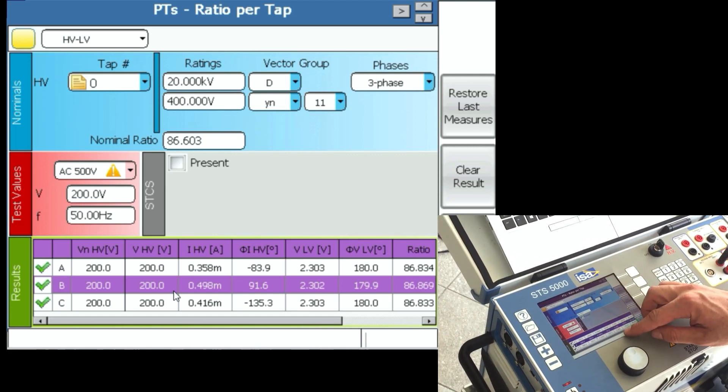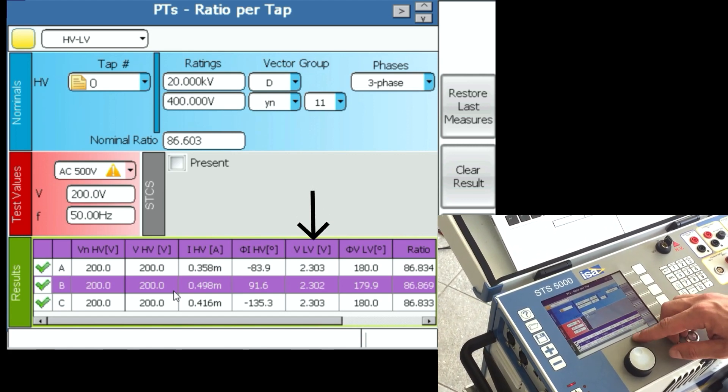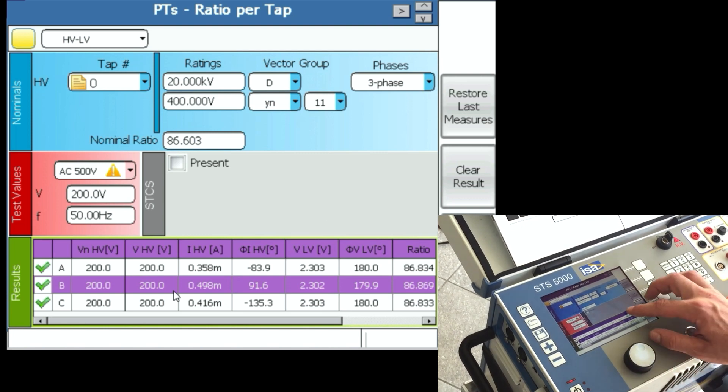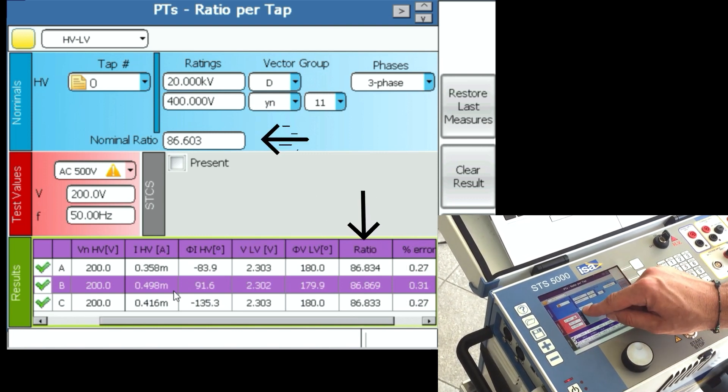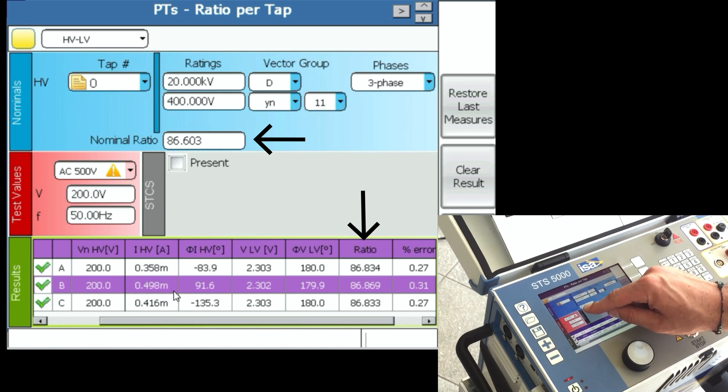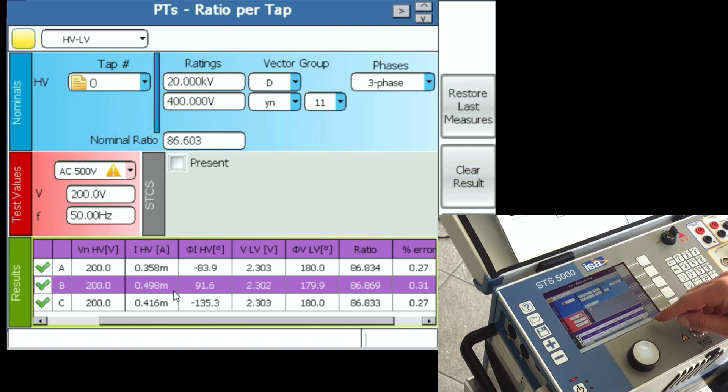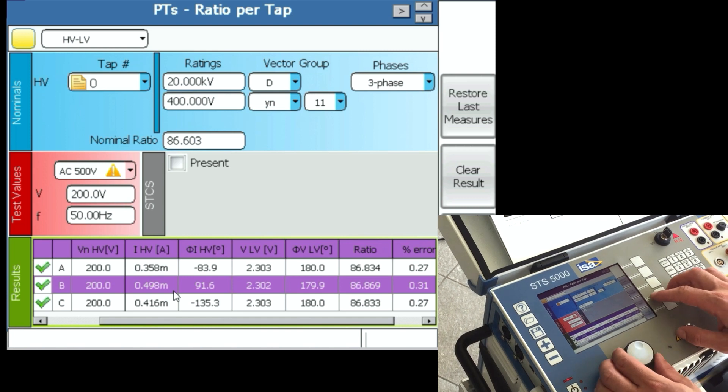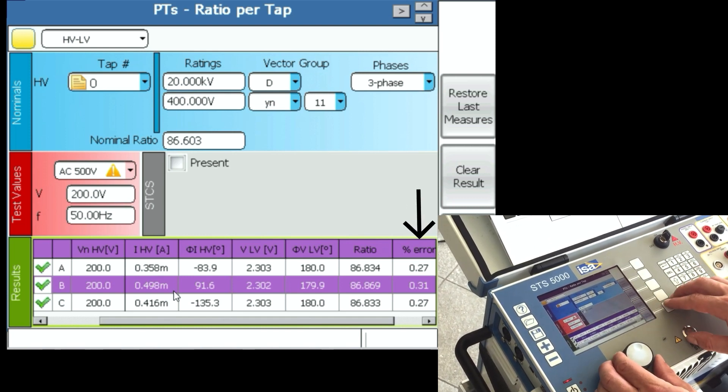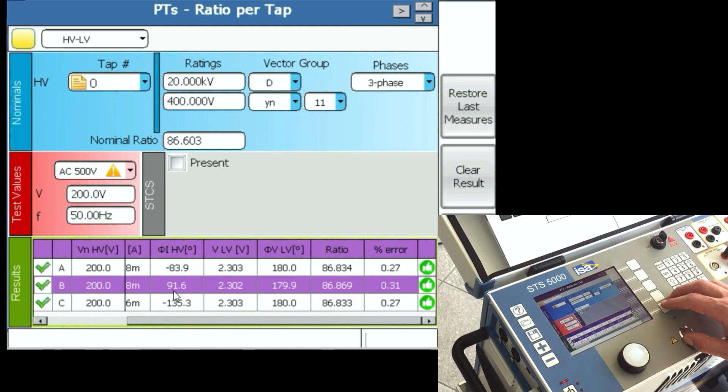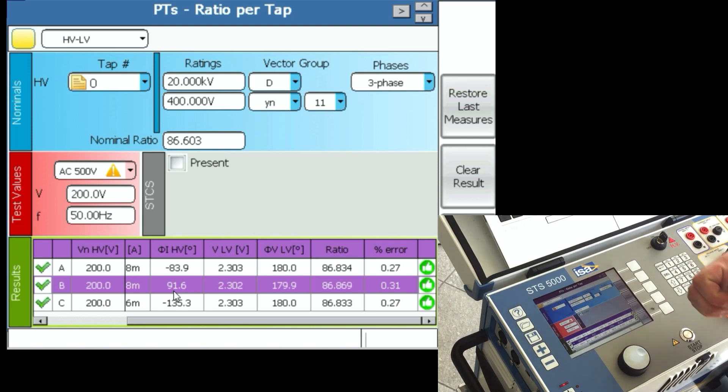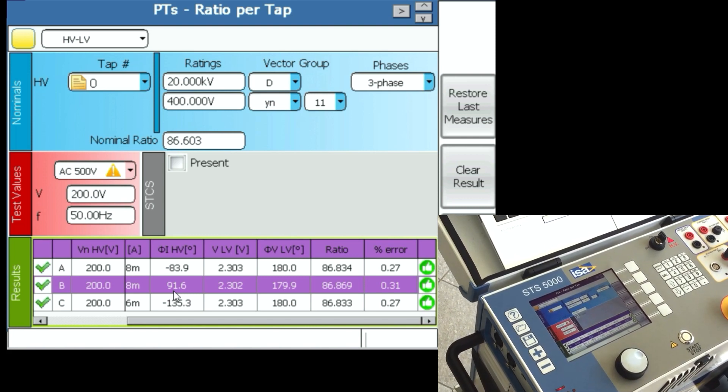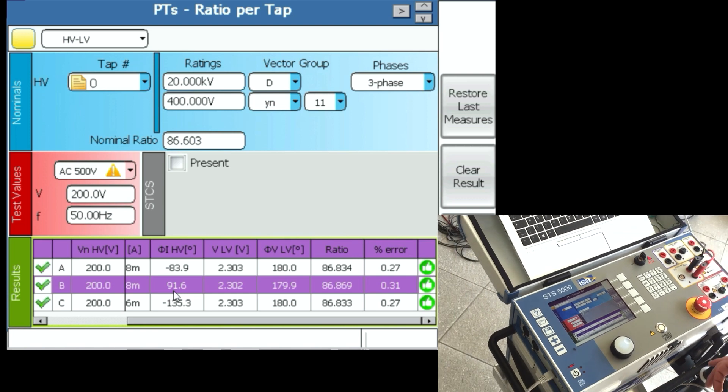This is how much we measured on the secondary side: 2.302 and 2.303 volts. And these are the ratios we've gotten. Let's remember that 86.6 is the nominal. We got 86.8, which is an error between 0.27 and 0.31, which are both less than 0.5. That's why we have good results, and this is how you can do a ratio test.